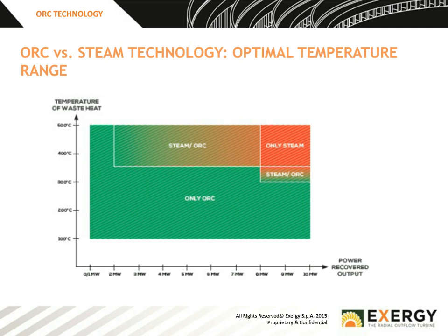Now, you could use ORC in any application. So at very high temperatures and very large sizes, you could still use ORC. So why don't you? The reason is it becomes less cost-effective than steam. However, if there's a specific restriction in the environment, such as a lack of availability of water, it may be a conscious decision to use ORC even when it is not the most cost-effective or the most efficient solution. However, generally, it is better to use steam when you get to high temperatures of exhaust.